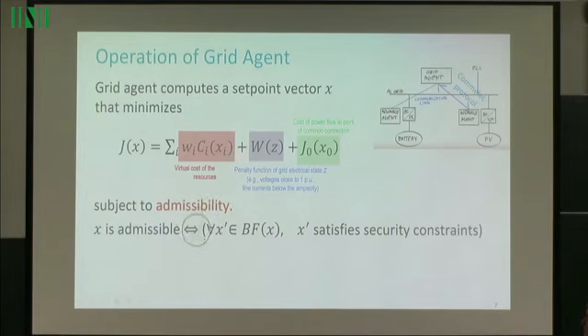But it still needs to make sure that what we call admissibility holds. Admissibility is the fact that if the grid agent instructs all the resources to do xi here, they will not necessarily do xi - they will do something that is in the advertised belief functions that correspond to that set point. So we say that a collection of set points is admissible if, for any practical implementation that's within the uncertainty bounds, the implemented value satisfies the security constraints, which are voltage magnitude and line current constraints here.